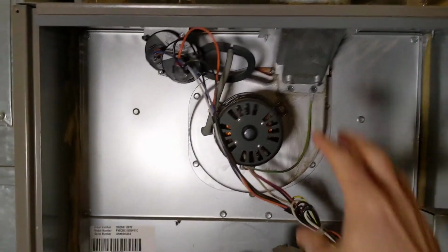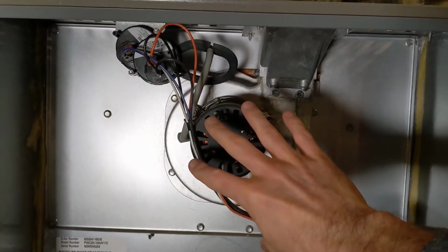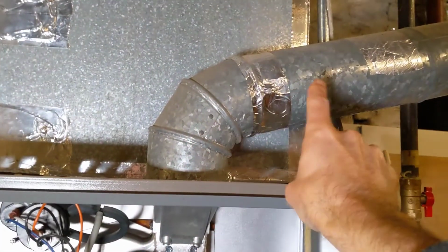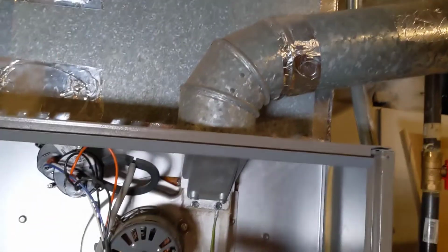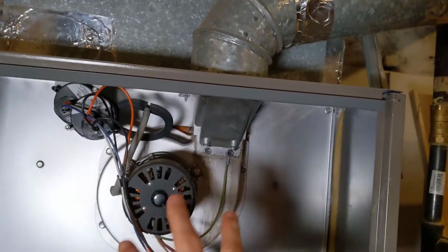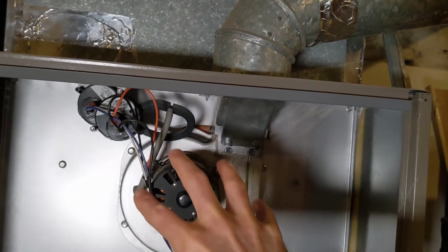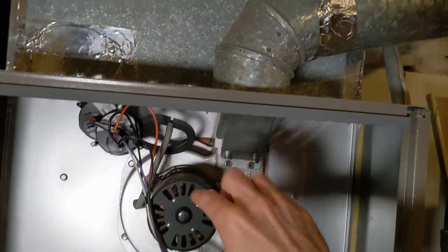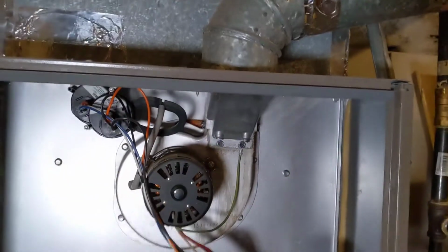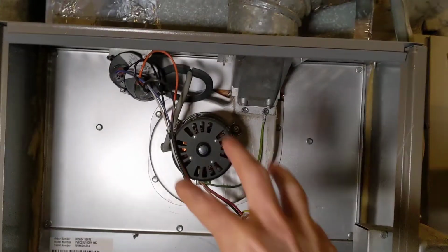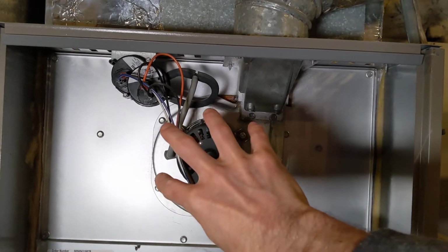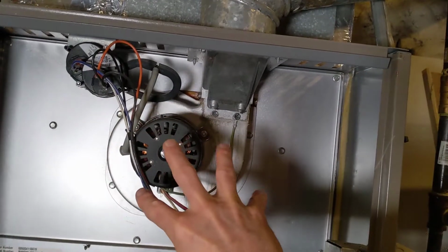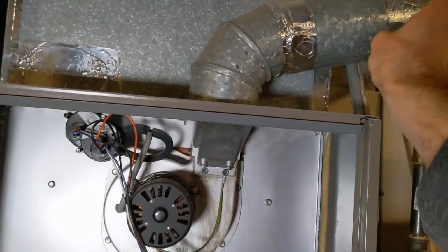You'll typically have a motor at the top here that's connected in some way to your exhaust. Now, if you have a 90% furnace, this might be a PVC pipe, but either way, you'll have a small motor around here that pumps out exhaust, and that's called the inducer or draft motor. What it does is it induces a draft. It's just a motor that spins into the squirrel cage here and pushes exhaust air out.